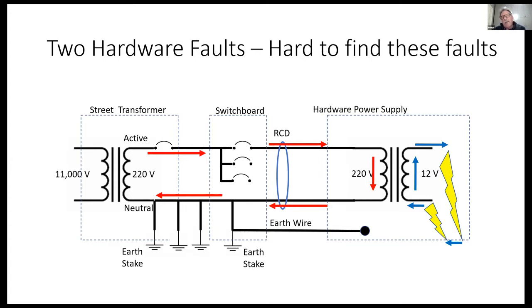But the important thing here is, we've got some sort of fault on the secondary, and the current in the primary is still staying in the active and the neutral. There's no current flowing in this earth wire on the primary side, on the 240 volt side. So that's a theme you'll start to see: as soon as you put some sort of isolation in, the primary side, or upstream side, of that isolator doesn't see any unbalance at all, and never will.